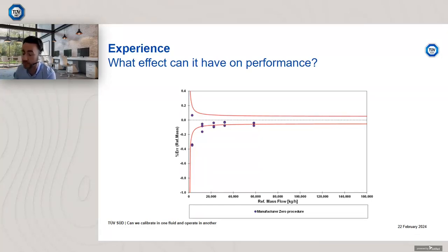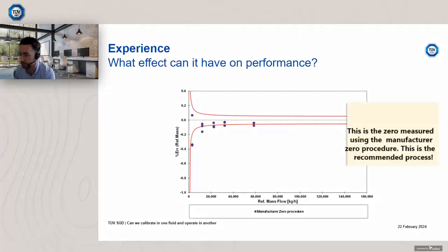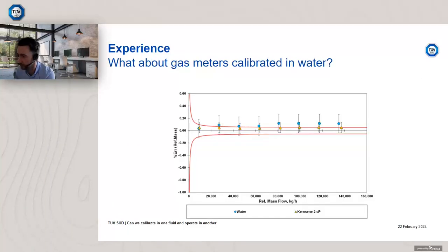So this is critical if you're trying to use a gas meter and calibrate it in liquid, where zero effects will potentially dominate. You will then apply that gas meter in use, having calibrated it at a very low mass flow rate for liquid, and the zero effects could potentially dominate, and you could be significantly out of specification and be operating with a very large uncertainty. So just to let you know, the zero measured using the manufacturer's zero procedure is the recommended process, even though we know there's potentially a slight offset there, not a perfect zero.